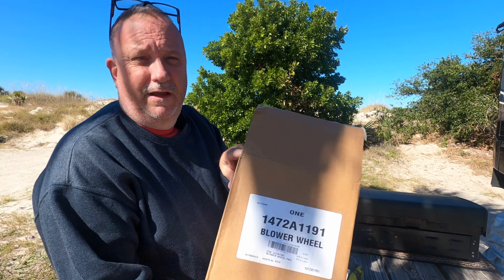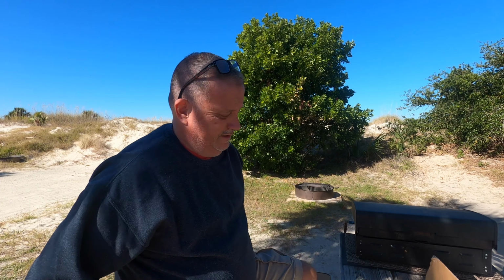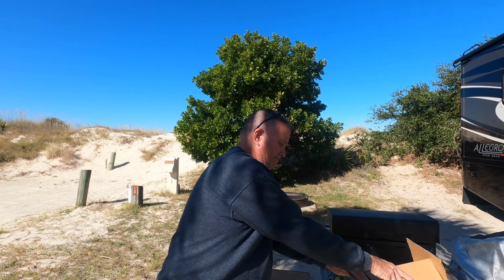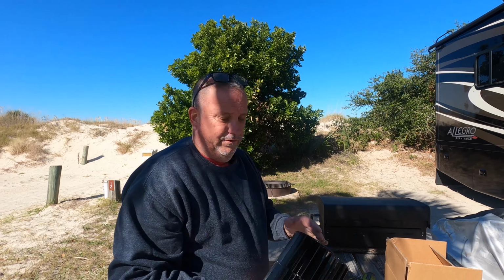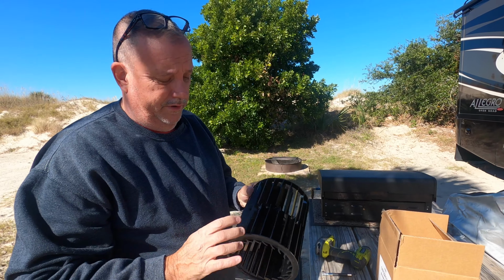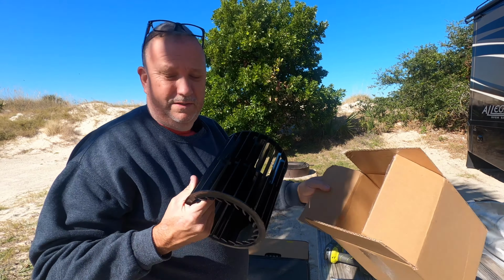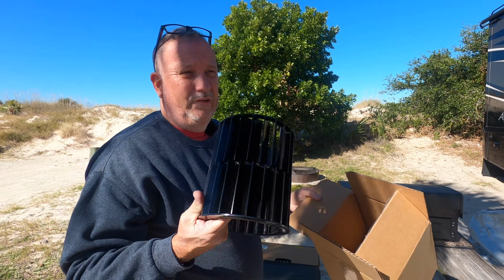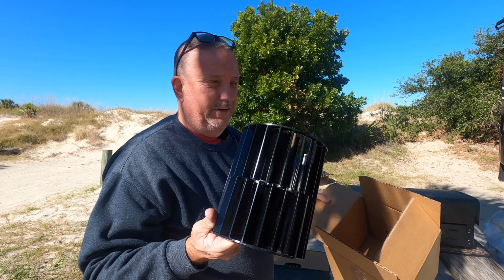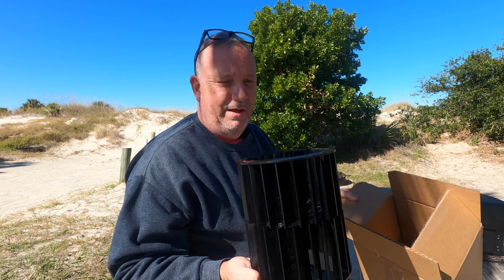And you're going to need the famous blower wheel. This is the third one we've done in about 3 months. I just ordered today. I was able to find some aluminum squirrel cages. You can see these are plastic. And when we take the old one apart, we'll see what disintegrated. But usually one of these fins breaks or something like that. So I have aluminum ones hopefully coming, because these just aren't working. These used to be $49, now they're $65 plus tax, and they're made in China and they just keep breaking.